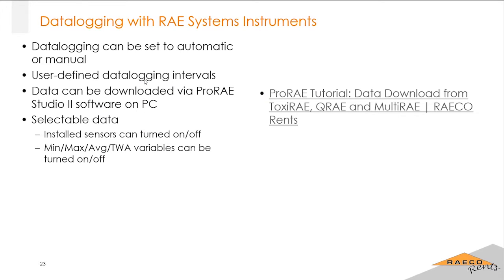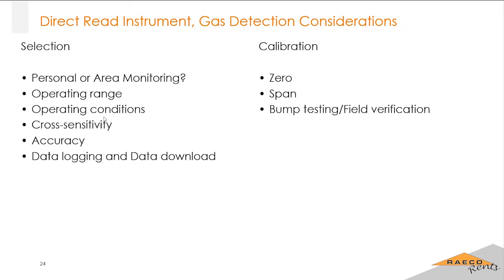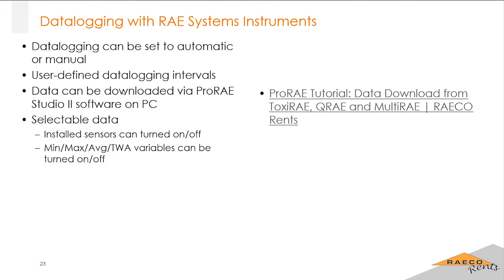So let's go over the logistics of sampling with this, your data logging. If you were to rent the equipment, we set them to automatically data log every minute. Once you turn that on, it's going to be data logging. You can set that to automatic or manual. There are user-defined data logging intervals, so you could have it measure every second, every 5 seconds, every 10 seconds, every 10 minutes—totally up to you. Then the data can be downloaded from ProRAE Studio software.